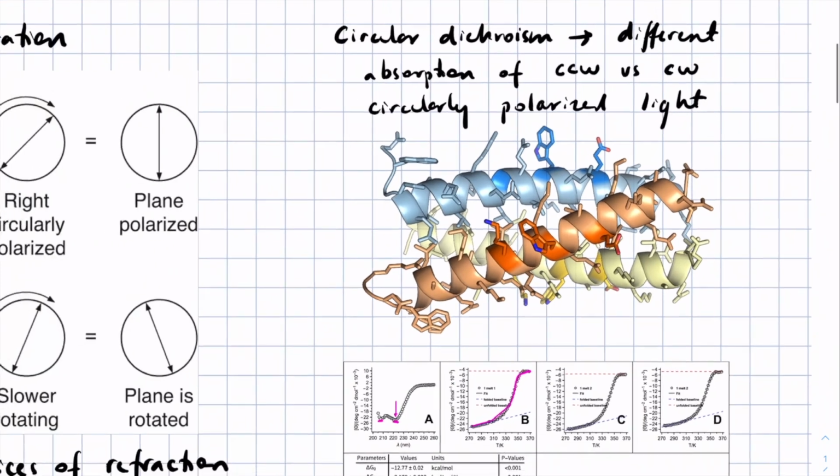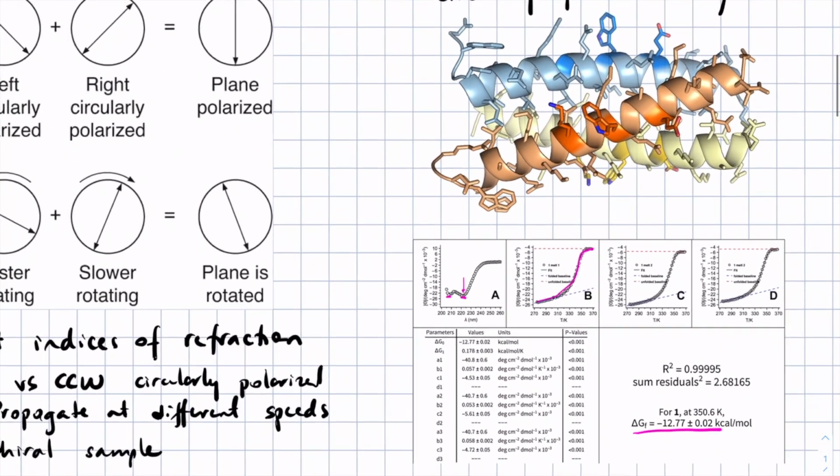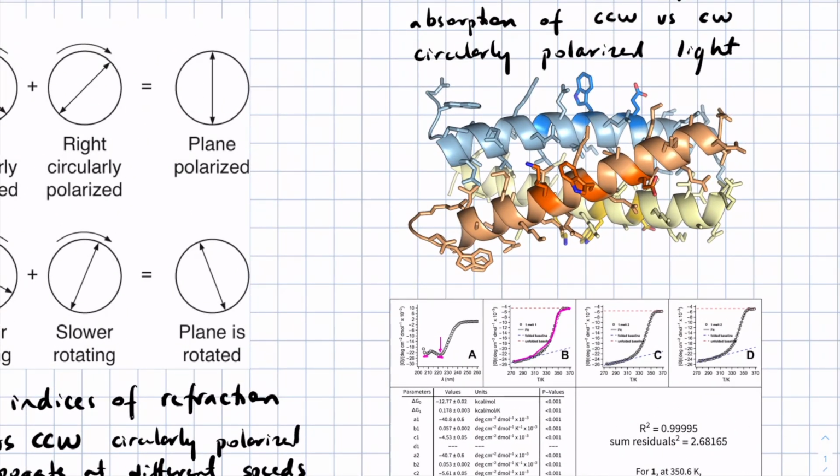To use the CD instruments over in life sciences, you have to have a certain kind of quartz cuvette. You might imagine that because this is a technique that's sensitive to polarization, you don't want your cuvette to have any defects that might itself impact the polarization of the light that you're passing through the sample. So these are very tiny cuvettes, 1 millimeter path length.